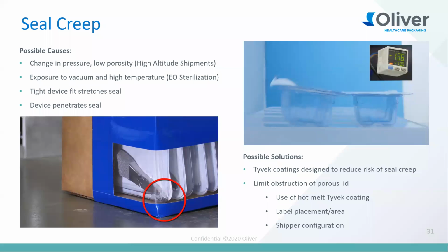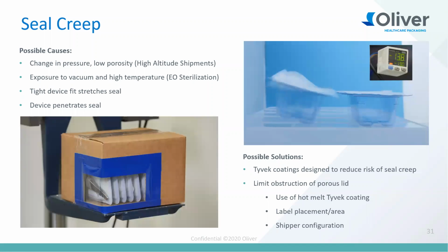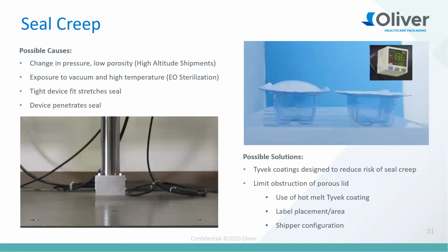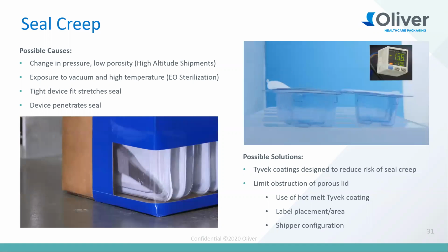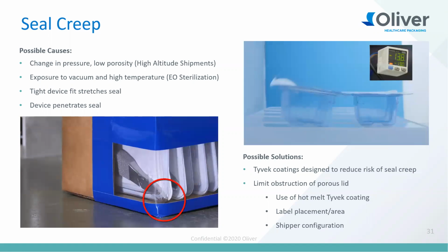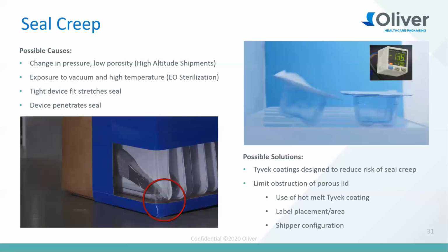Also, in this video that we can play at the bottom, the device can penetrate the seal. This is the drop test that we showed earlier with a window into the shipper, and you can see the device has penetrated right through the seal. Just like Tommy mentioned earlier about different holes in the package, different types of seal creep could have different causes, so you really want to understand where this is coming from. One of the most unknown places, when people come to us with this failure, is the EO sterilization chamber. We have them check it first and ask, are you blocking the porosity?